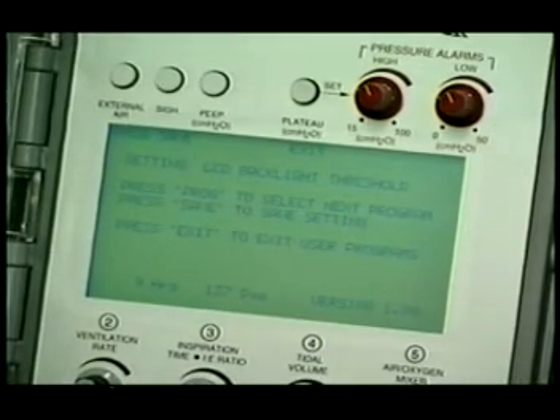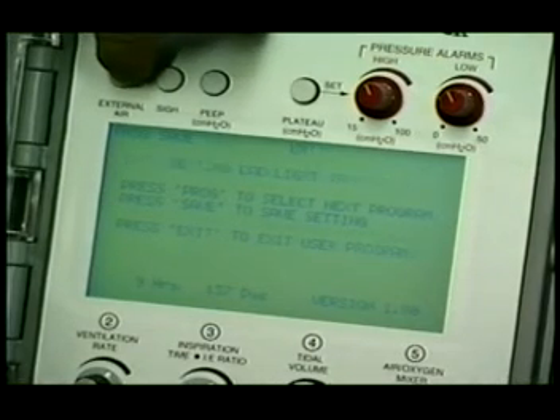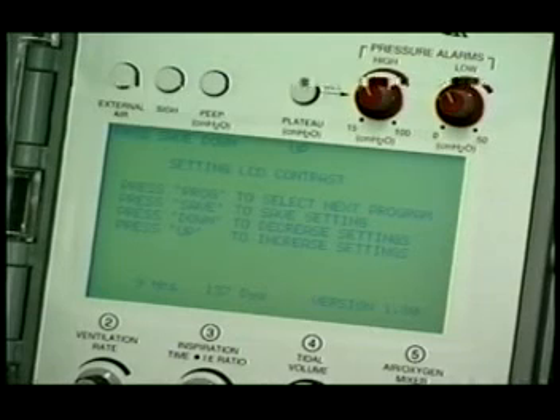At the bottom of each menu is information that indicates the number of cumulative hours of operation and cumulative days since the last preventive maintenance was performed, and the software version contained within your ventilator. The first menu allows you to set the LCD backlight threshold. The threshold represents the lighting level that will cause the LCD to illuminate. Follow the instructions. If you want to reset the threshold, press the push button above the word Save. If you wish to exit the menu, press the push button above the word Exit. The next menu allows us to set LCD contrast between activated characters and their background. We can adjust contrast upwards or downwards.